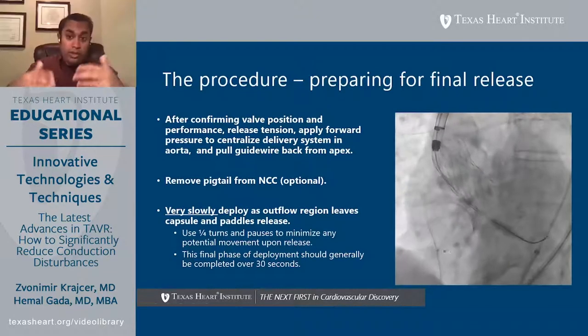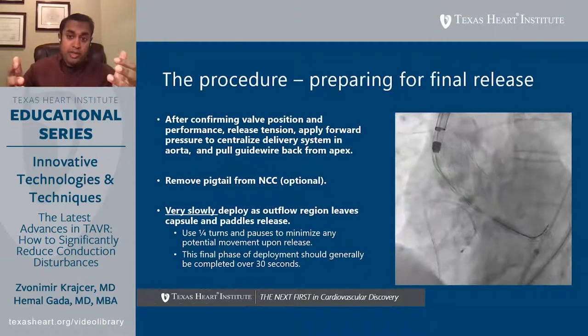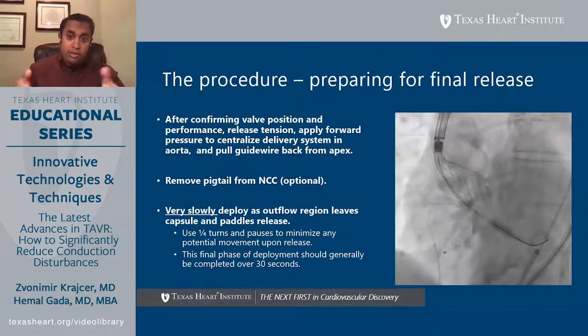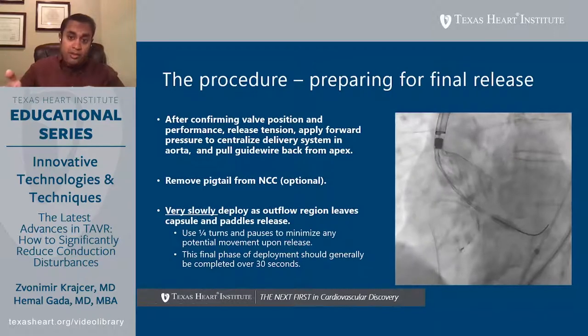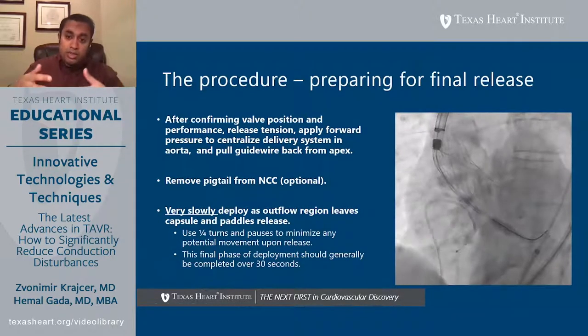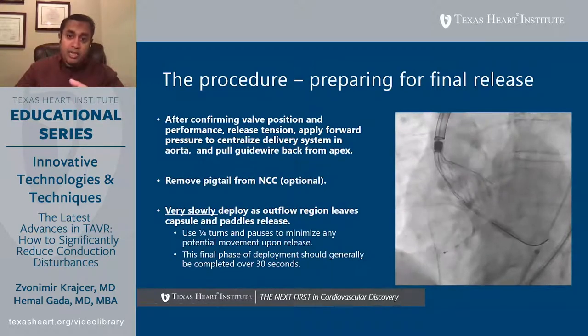So we were very quick to get to this point of the procedure and we did our assessments. Now we slow everything down. The wire is pulled back so it's barely out of the nose cone. We're basically doing a 15 degree turn on the delivery catheter every 10 to 15 seconds, allowing the valve to expand in that annular plane to abut the calcified tissue for the nitinol to warm up—all of those things that will keep the valve nice and stable.